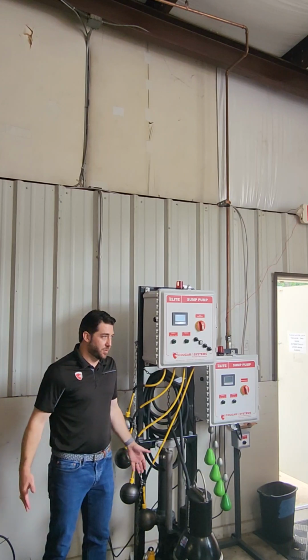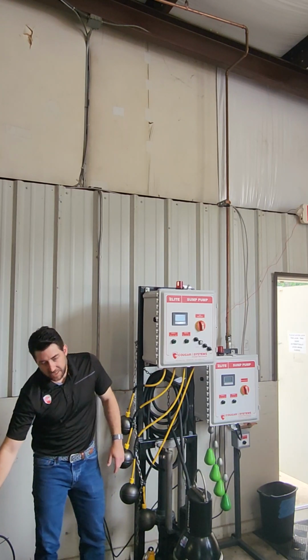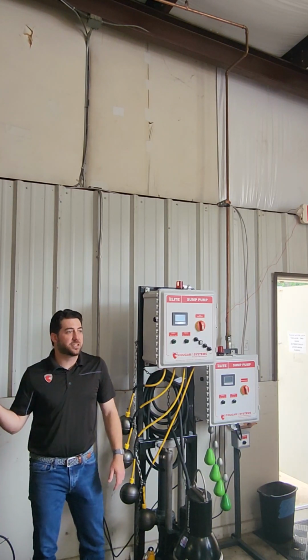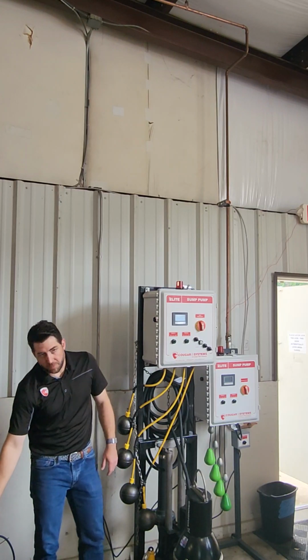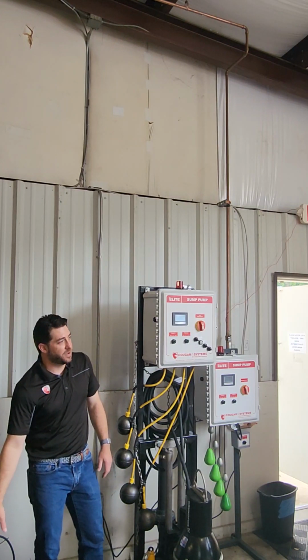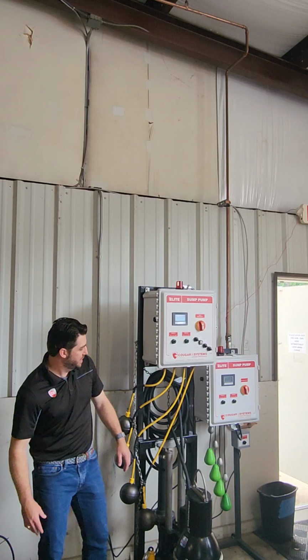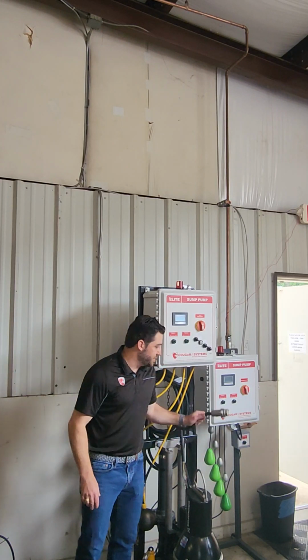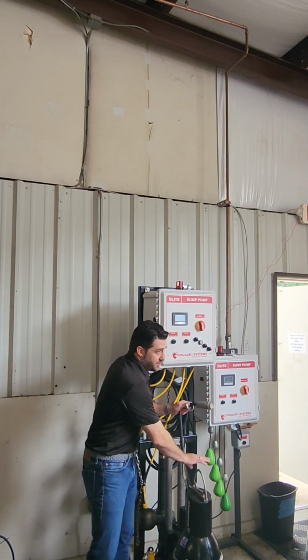So if you do have a customer that floods, I'm going to recommend that they change their pumps at the same time as they change their panel and everything else, because eventually their pumps are going to fail when that moisture gets down into the motor. With these, you can change the cable. You don't have to change the motor.